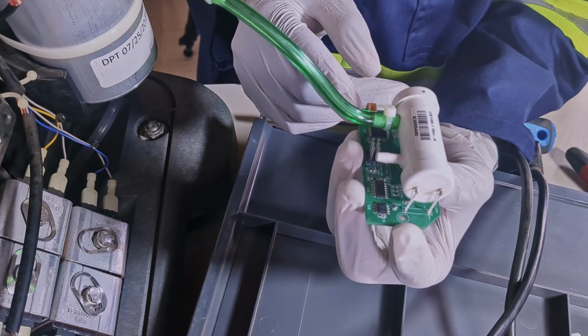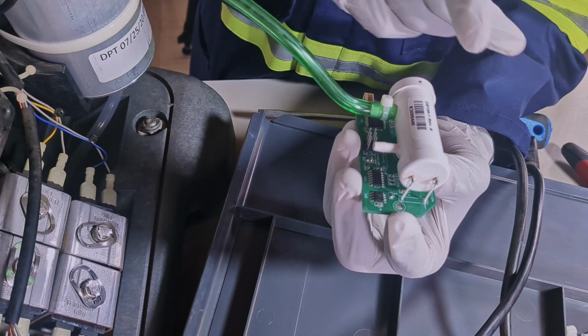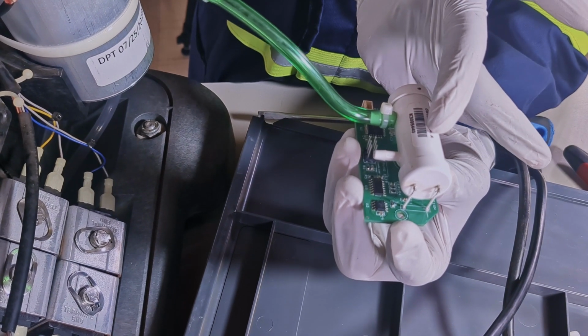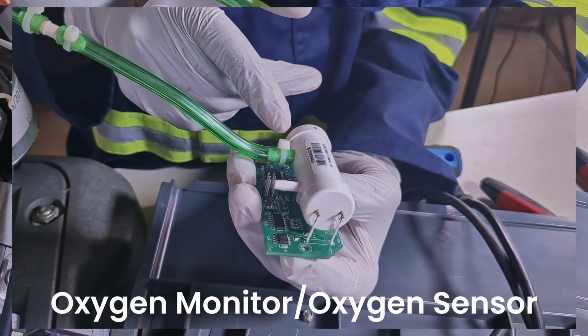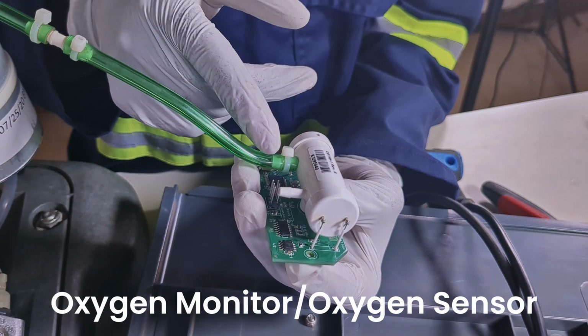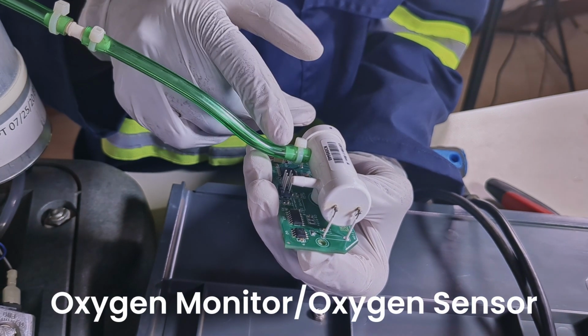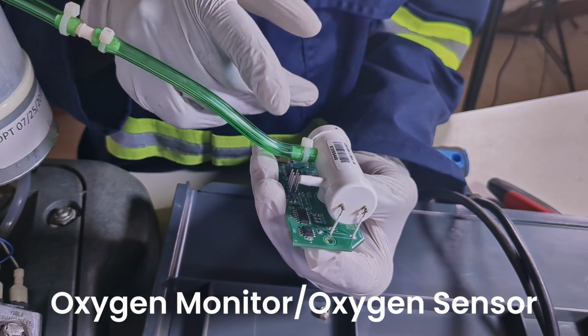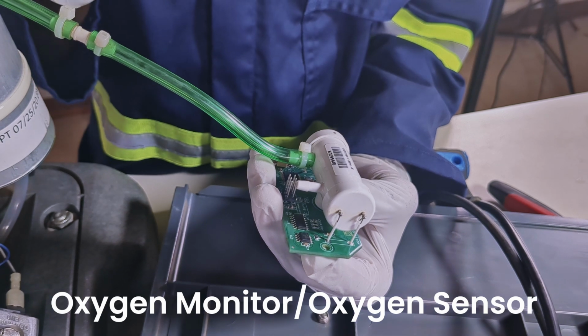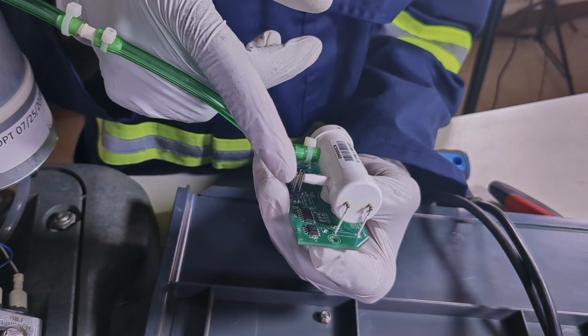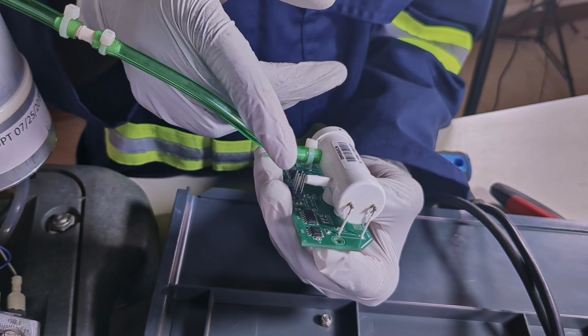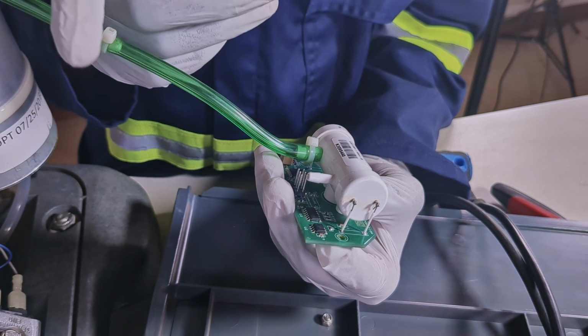This is the oxygen monitor circuit board, and here is the oxygen monitor. The oxygen monitor has 2 connection ports. This port is for the oxygen inlet and it is connected to the inlet or the flow meter, while this port is for the oxygen outlet. So it connects the tubing that goes to the oxygen outlet.